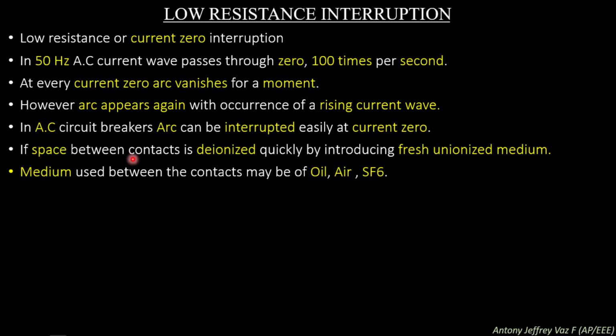The contact space where the arc is struck will be deionized quickly and filled with fresh un-ionized medium so that the ionized particles are removed and the conduction of the arc is stopped, so that the arc cannot restrike when the rising current wave occurs after current zero position.